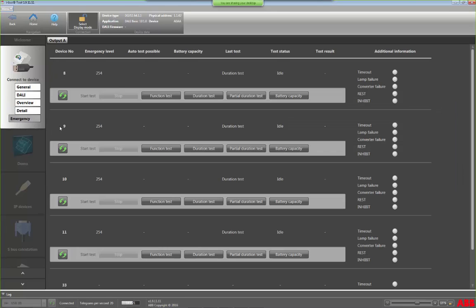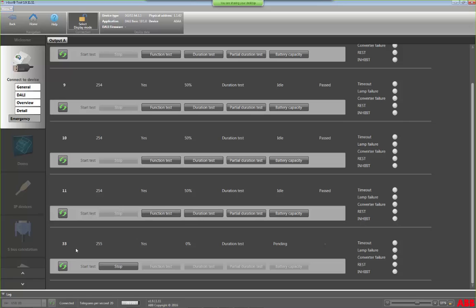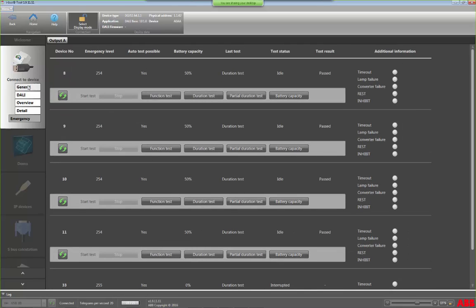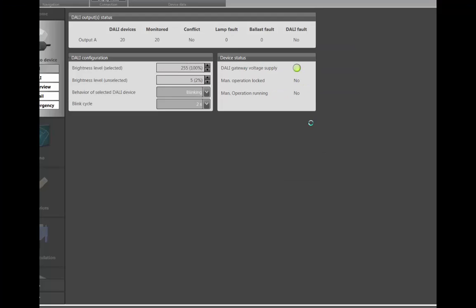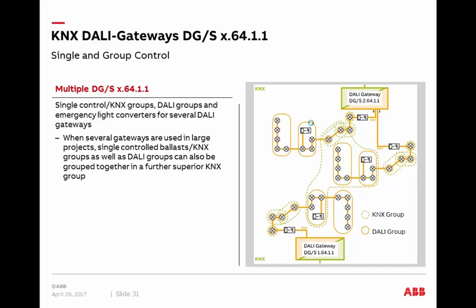The last menu is about the emergency converter. Multiple emergency converters can be managed here — for example, converter 33 is currently running a duration test which can be stopped. You can also start a function test or duration test, or read out the battery capacity. This concludes the overview of the ETS parameters and a short introduction to the i-bus Tool. There is a wide range of additional new parameters and settings available. I now hand back to Thorsten for the final slides.